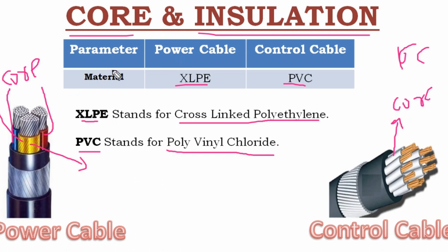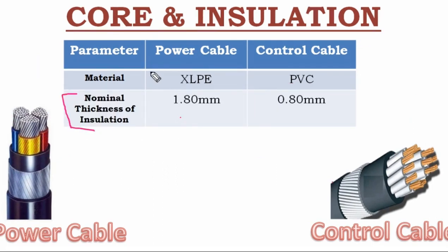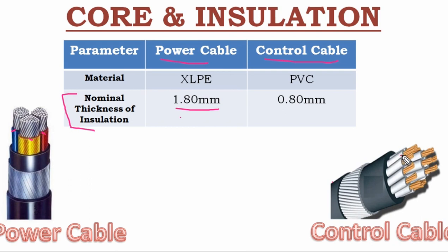Regarding the nominal thickness of the insulation: in the power cable, the nominal insulation thickness is 1.8 mm, and in the control cable, the nominal insulation thickness is 0.8 mm.